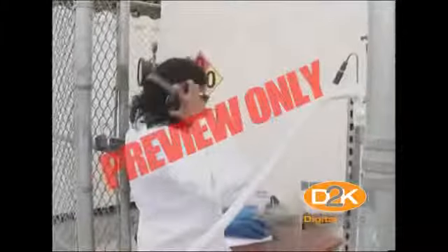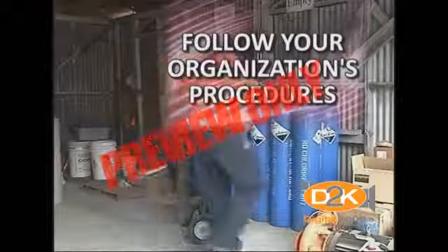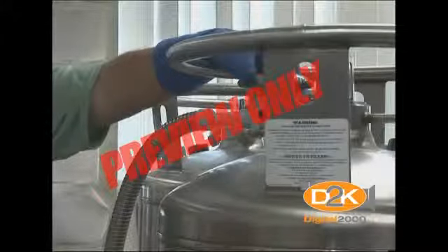Depending on the hazard, examples of potential personal protective equipment, PPE, include goggles sufficient to completely protect the eyes when any connection is made or broken to a cylinder or valve. This could include, but is not limited to, tight-fitting safety goggles in conjunction with a full face shield. Fabric or leather work gloves and sleeves might be required whenever a cylinder is moved or transported, or to protect from the hazard of cryogenic gas coming into contact with exposed skin. Face shields and goggles shall be worn during the transfer and normal handling of any cryogenic liquid.